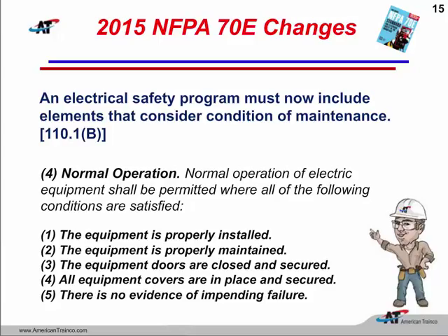The next one, the equipment has been properly maintained. Well, this is going to be according to manufacturer's instructions, so a lot of our equipment probably is not going to fall underneath this particular requirement. The equipment has been properly maintained. Even if we took just a regular molded case circuit breaker, the chances that we properly maintained that circuit breaker over the years is probably pretty slim. So they're going to want documentation of this. So immediately, if we can't document that the equipment has been properly maintained, well, normal operation is not going to happen. So what does that mean? Well, that means that now we are going to have to wear some type of personal protective equipment to protect us from either shock, arc flash, or arc blast to operate that equipment.